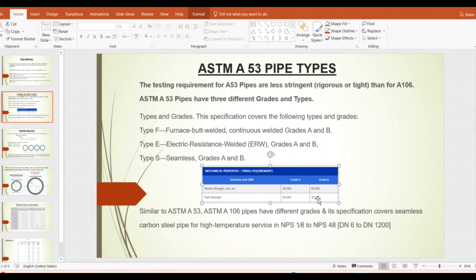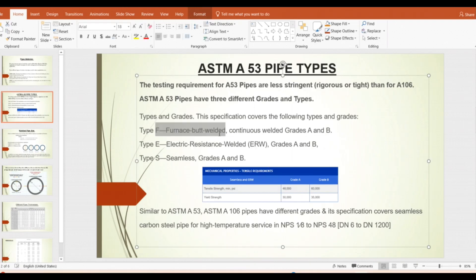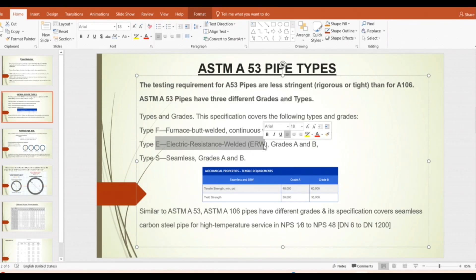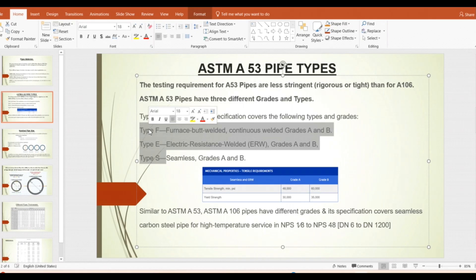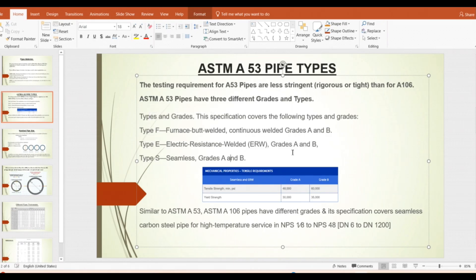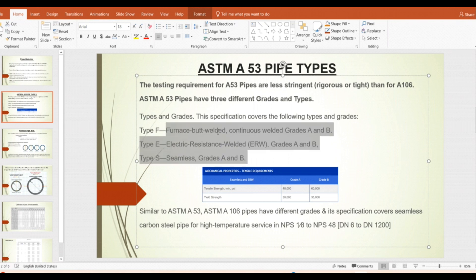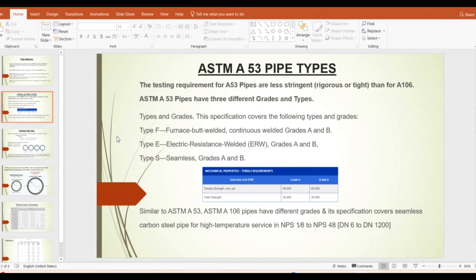For all chilled water applications we use Grade B material for its higher tensile and yield strength compared to Grade A. Type F is furnace butt welded, Type E is ERW welded (pipe comes with a weld seam), and Type S is seamless (pipe comes without welding). The type describes how the pipe is manufactured, and then the grade — A or B — is specified after that. This is how we classify pipes: ASTM A53, A106, API 5L, then the type, then the grade.